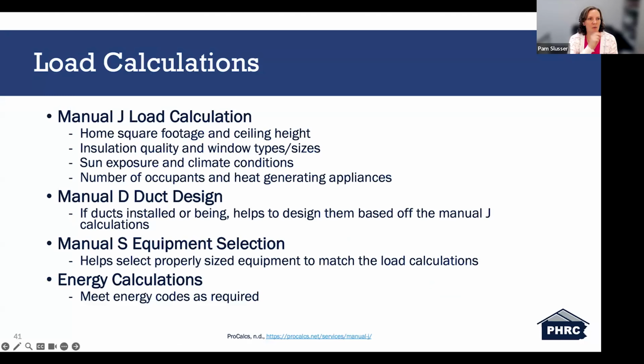Talking about sizing, load calculations. When they're doing the sizing, these are load calculations that would need to be done to meet code requirements. Starting with the Manual J load calculation, this determines the exact heating and cooling loads of a building. What this step looks like is you have the square footage of the home and the ceiling height. And then you look at the quality of the insulation and the type and size of windows, the sun exposure of the home, including shading and orientation, the climate zone, and internal gains from occupants and appliances that produce heat. The goal of the Manual J is to avoid oversizing and undersizing. And then you have a Manual D. This is for duct design.